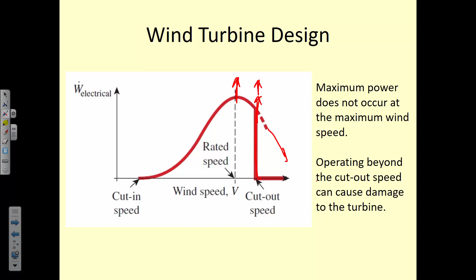Yeah, so the cutout speed is a safety mechanism, and if for some reason those brakes fail and they don't turn off and that turbine continues to spin at higher and higher speeds, then you can have catastrophic failure. So there's a safety factor built in here, right? It's not like right at the cutout speed is when it would explode. It's somewhere further along in velocity, but you do it such that you can turn the turbine off and be able to brake it, because as it starts moving faster and faster, those inertial forces are so great that it would require a greater amount of braking power to turn it off. So the cutout speed is some value designated based on economic cost and possibility of failure for each turbine.